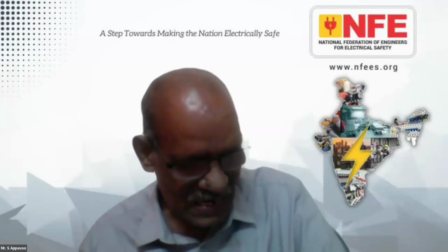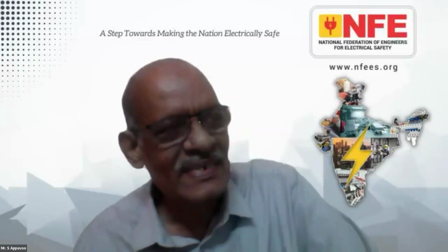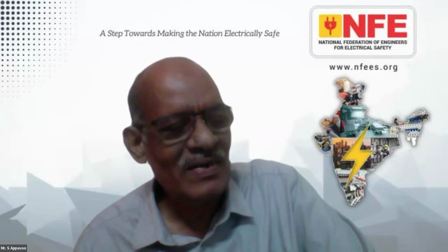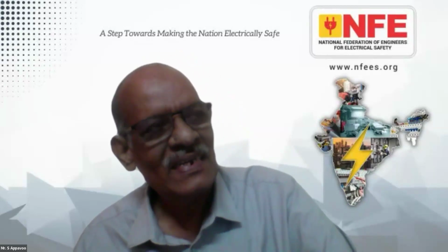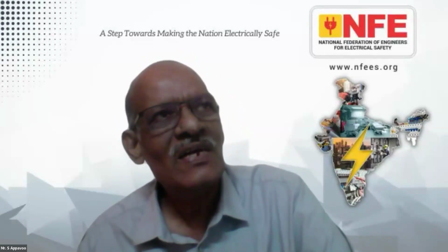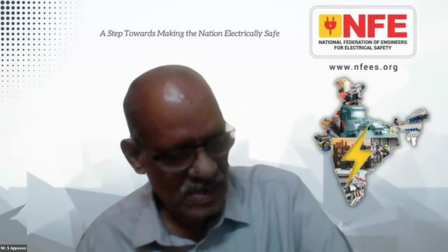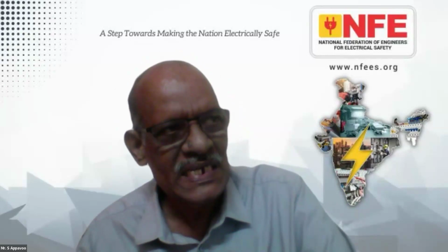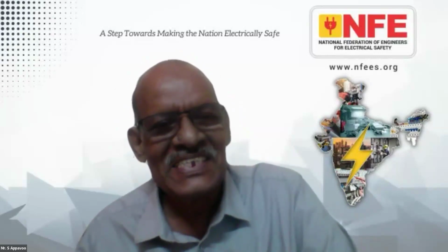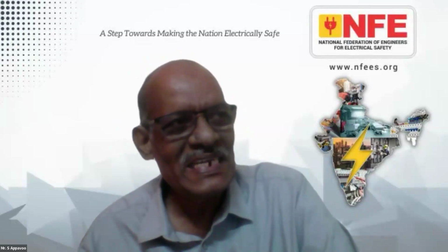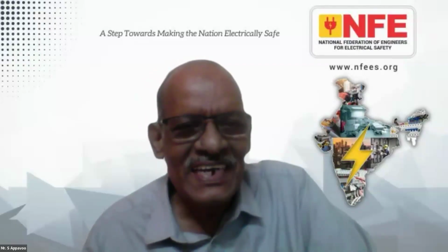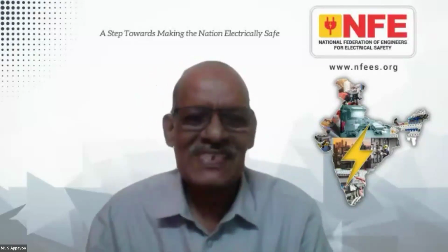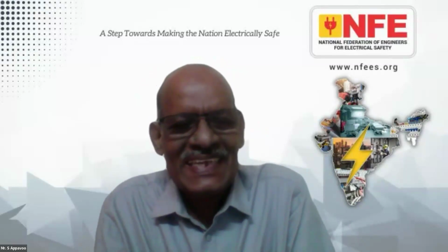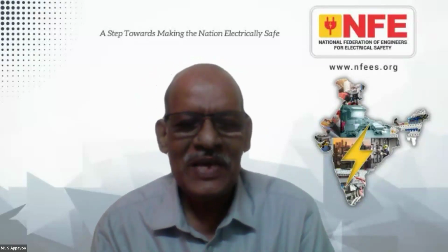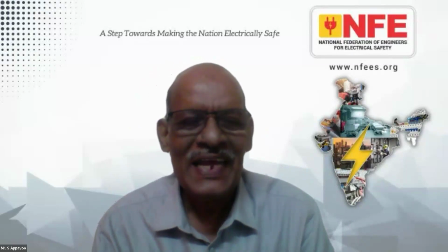Nicely you have explained. Also, you have pointed out an important thing: implementation. We know the problem and the issues of harmonics. Is it implemented? Strictly speaking, as you said, Tamil Nadu and Maharashtra have come out with some implementation model, and the regulatory commission has also notified, but actual implementation is yet to take up. There are still some difficulties in measurement, but we need not wait, because it's a headache for the consumer himself. Within the consumer, compliance with reference to the grid is one thing that can be implemented, but harmonics will make you implement it compulsorily when you find your system goes wrong.